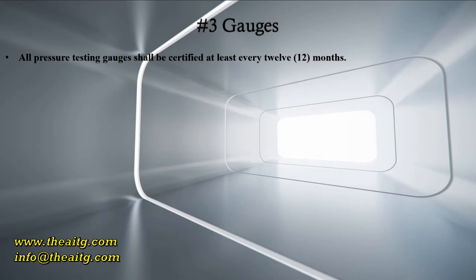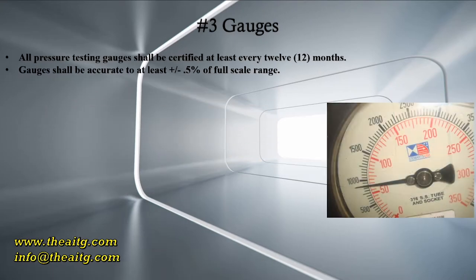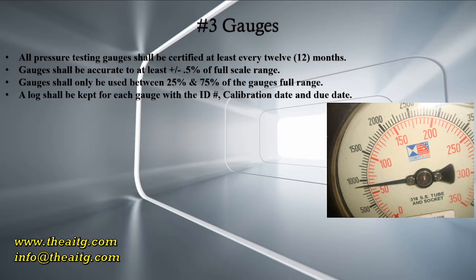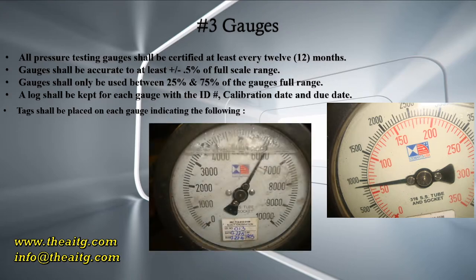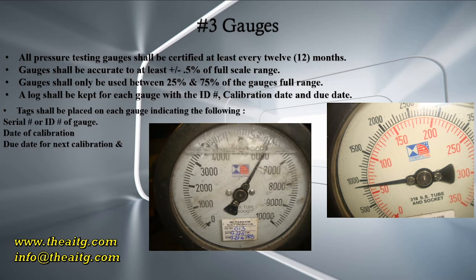Gauges: all pressure testing gauges will be certified at least every 12 months. Gauges shall be accurate to at least plus or minus 0.5% of the full scale range, and shall only be used between 25% and 75% of the gauge's full range. A log shall be kept for each gauge with the ID number, calibration date, and due date. Tags shall be placed on each gauge indicating the serial number or ID number, date of calibration, due date for next calibration, and company performing the calibration.